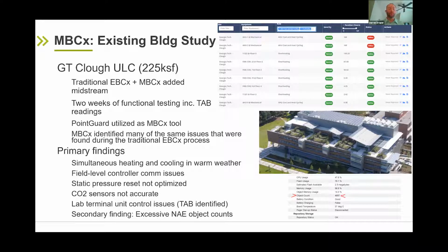But the interesting thing is that in the two weeks or so of testing, we found a lot of the same things using the MBCx tool from Point Guard as we did with the traditional existing building commissioning process, over a more laborious activity. So it was a really interesting case study where we let the two activities complement each other, where we did some field testing, particularly some TAB measurements that turned out to be really important for field level activities in the space level results, and then a monitoring-based commissioning platform to supplement that.